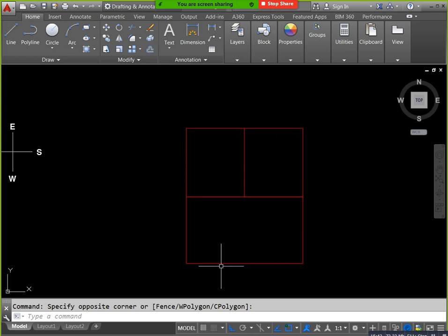But for the partition wall, when you come to the inner portion where both are conditioned spaces, you don't need to calculate this one or add the heat, because we don't have any heat transfer here. When you have heat transfer, then you can consider that partition wall and add that heat also. But here we have no heat transfer.